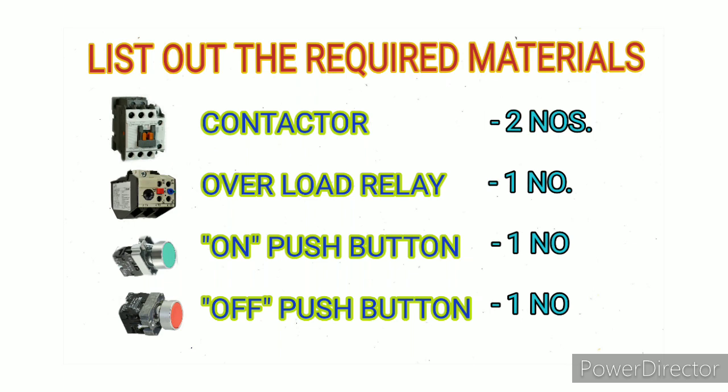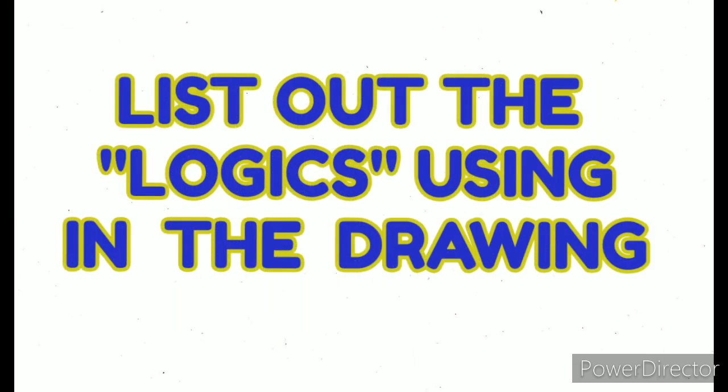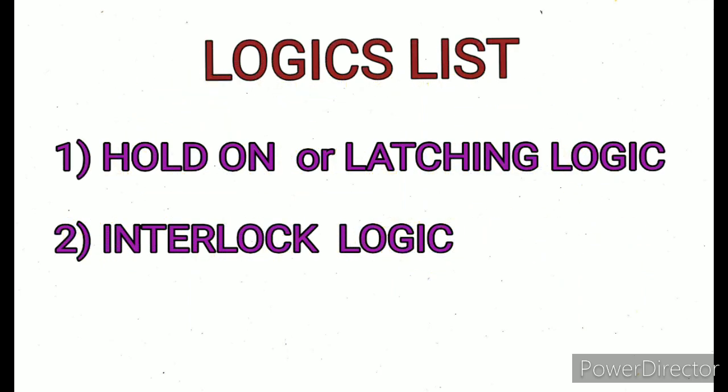Next step, we need to list out the logics using in the drawing. We are using two types of logics: hold on or latching logic. Next one is interlock logic. The hold on logic is commonly used in starter diagrams. Interlock means at a time only one contactor needs to pick up. If forward is working, at that time reverse is not allowed to work. This is called interlock logic.